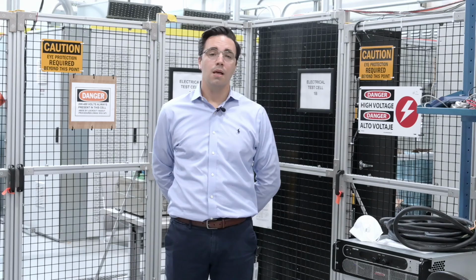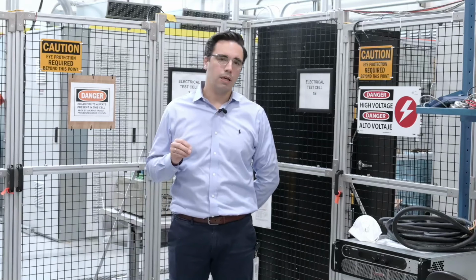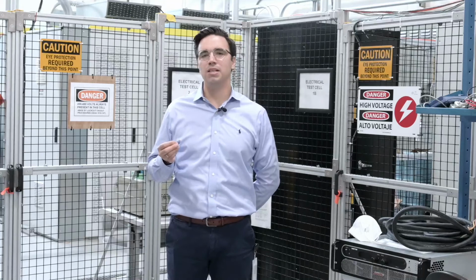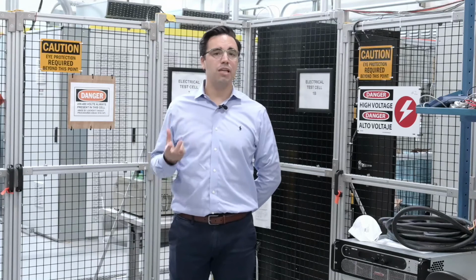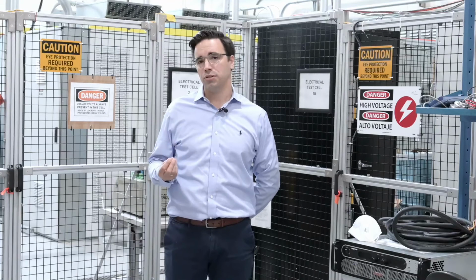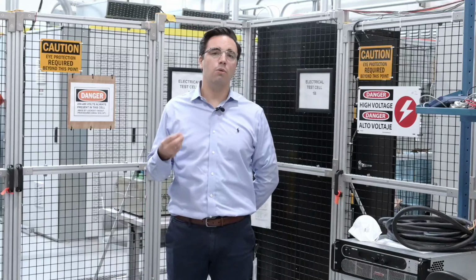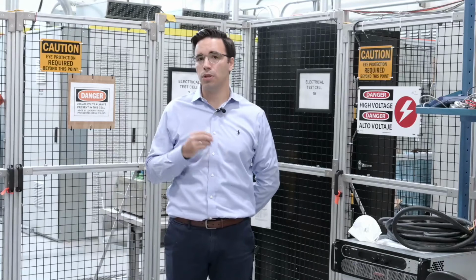Thank you, Pietro. And can you kindly explain to us how we can protect against this fault and which kind of circuit breaker we have to use? Yes, we can look at multiple options when we're trying to solve protections in these types of systems. The first option is the classical option. In this case, we have electromechanical breakers upstream and electromechanical breakers downstream. In this case, we're relying on energetic coordination to protect and coordinate protections in the system. Unfortunately, this method falls short because it will not be able to protect against the fault current coming from the main source and through the rectifier. Occasionally, it could also cause problems in protecting other power converters.